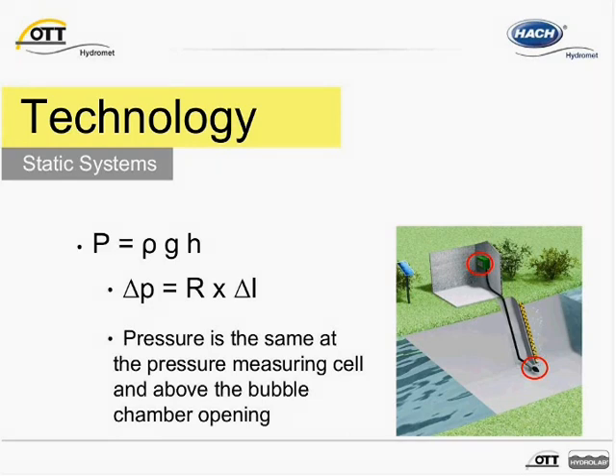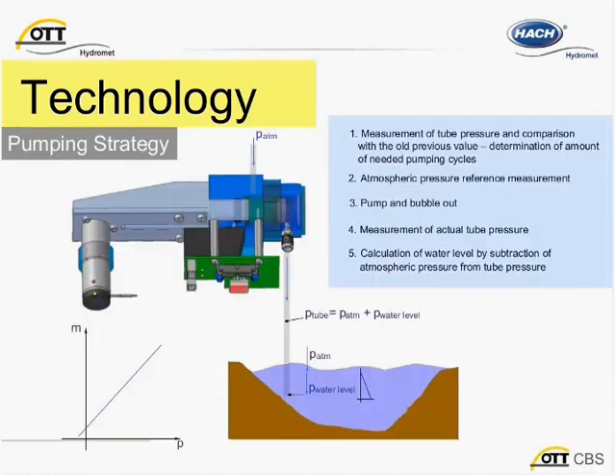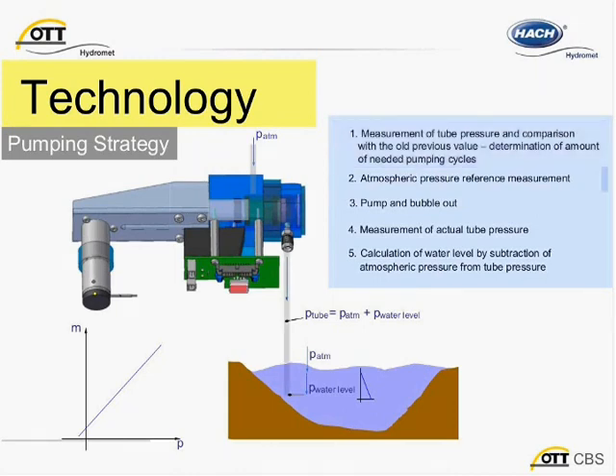With static systems, sources of error that result from changes in air flow are thus eliminated. To take a more detailed look at a static system, let's go through the intelligent pumping strategy of the CBS. Measurement of tube pressure, which is compared to the previous measurement, is step number one. This helps to determine the number of required pump cycles.